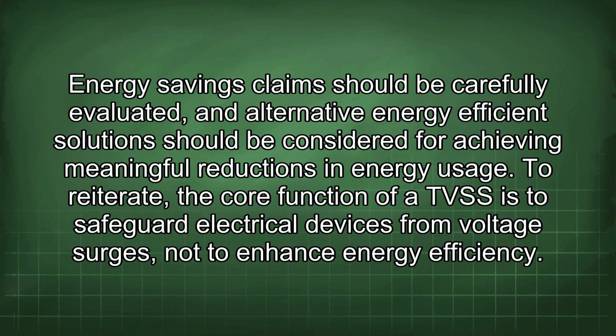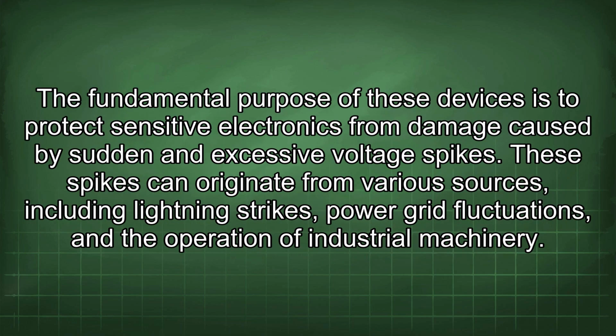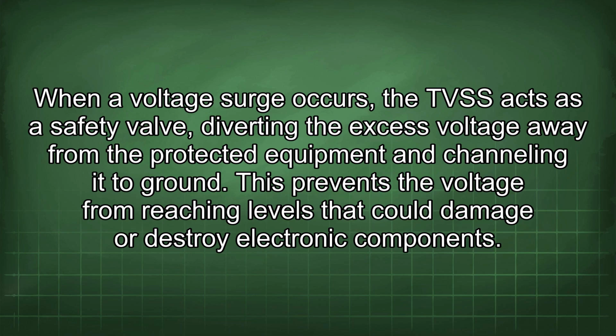To reiterate, the core function of a TVSS is to safeguard electrical devices from voltage surges, not to enhance energy efficiency. The fundamental purpose of these devices is to protect sensitive electronics from damage caused by sudden and excessive voltage spikes. These spikes can originate from various sources, including lightning strikes, power grid fluctuations, and the operation of industrial machinery. When a voltage surge occurs, the TVSS acts as a safety valve, diverting the excess voltage away from the protected equipment and channeling it to ground. This prevents the voltage from reaching levels that could damage or destroy electronic components.